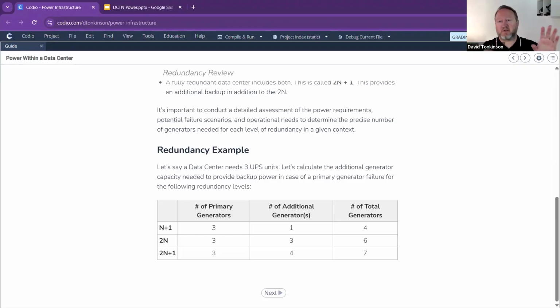The reason is they don't want to be unable to get that manufacturer out to repair it, unable to get the parts, or face a security issue with the software that runs that particular side of the generators. So if they've got a whole load of Volvo Penta generators on one side, they will buy a whole load of another company's generators to run the other side of the data center. That way, if there's a massive issue with one load and they can't get the parts, they know they've still got a full set of working generators from another supplier, with another service level agreement written.